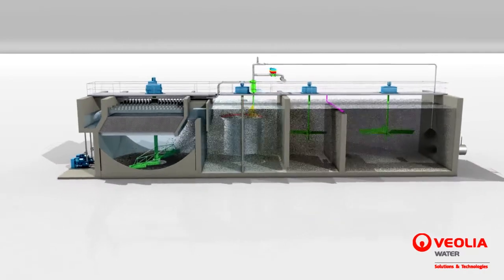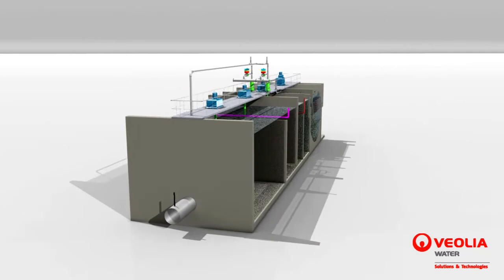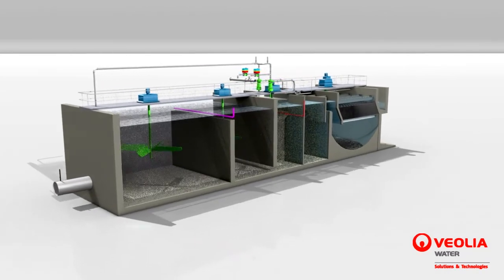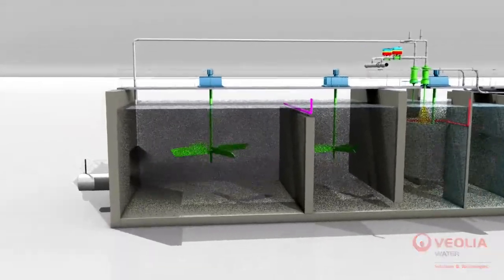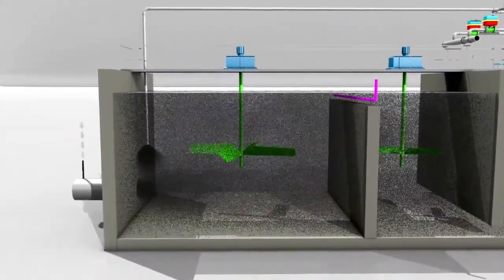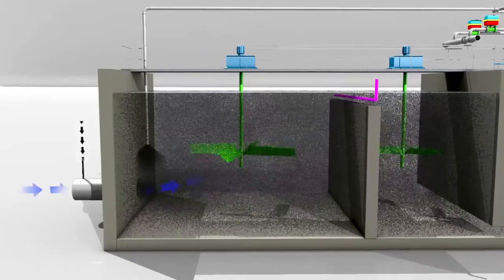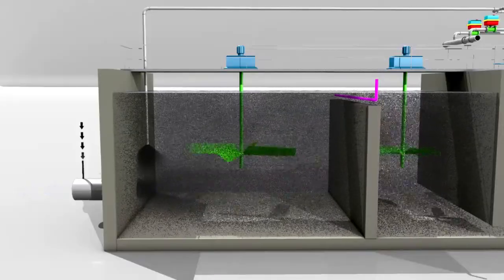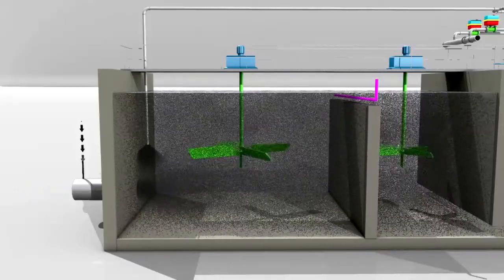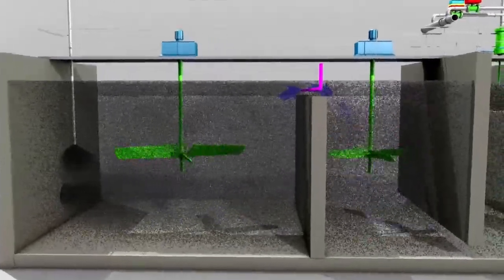The operating characteristics of Actiflo Carb are identical to those of Actiflo, providing it with the features of a rapid yet high-performance treatment process, ensuring the production of very high-quality water. After addition of powdered activated carbon, raw water enters the contact tank under vigorous mixing conditions to facilitate the adsorption reaction of the refractory compounds. Hydraulic retention time in this tank is typically 5 to 10 minutes.